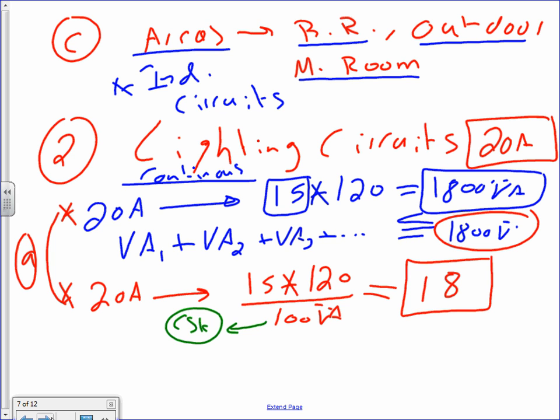That's the maximum you can pull out of this circuit, 1800 volt amp. Then here's how you do it. Take the volt amp of each fixture: fixture 1, fixture 2, fixture 3, add them all up. They have to equal or be less than 1800 volt amp, right?